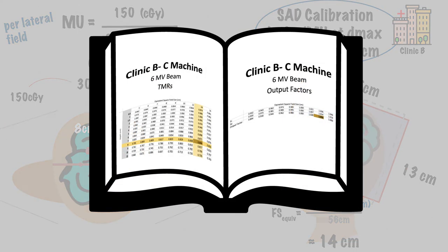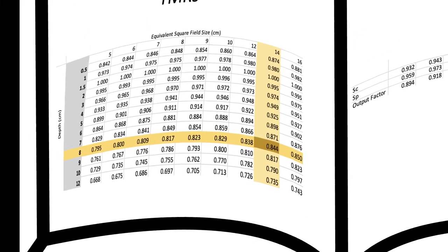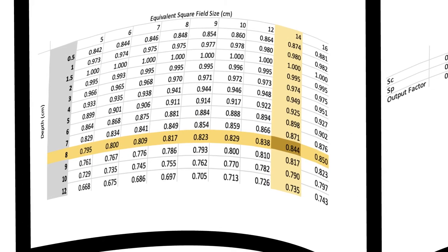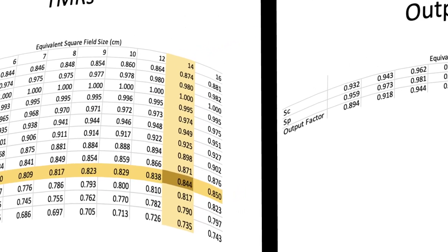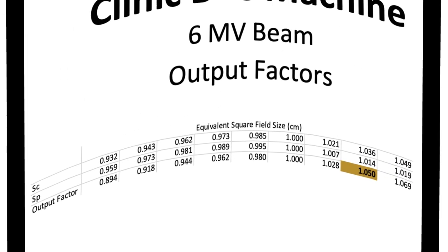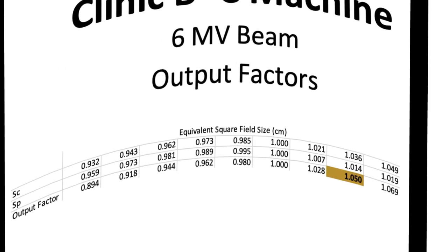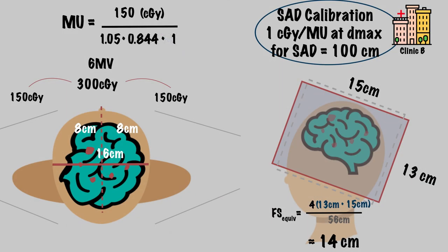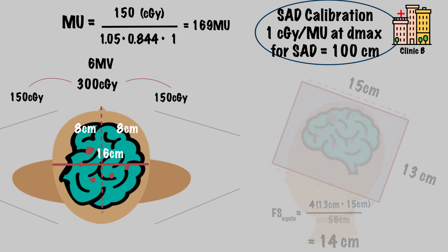For TMR, we find the cell corresponding to our depth and our equivalent square size, which is 0.844. And for the output factor, we just need to find the cell corresponding to our equivalent square field size, which is 1.05. Note that here the output factor is larger than 1 because field size is larger than 10 by 10 centimeters. Putting this all together, we have 150 centigray divided by our output factor of 1.05 times the TMR value of 0.844, which altogether equals 169 monitor units.